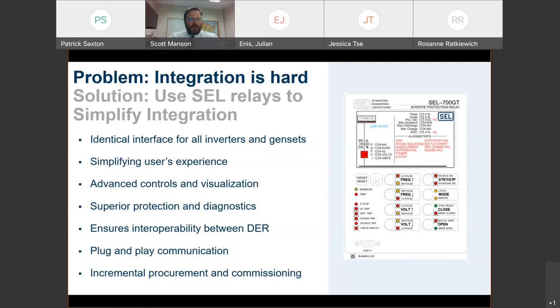Here's a great example, bullet point number two. Put yourself in the shoes of a utility technician. They have a truck full of laptops, full of tools, full of drivers, full of communication cables, and they have to maintain a fleet of inverters and generators and substation equipment and reclosers. It's an enormous amount of equipment they maintain. In one case, one technician had over a dozen different inverters from different manufacturers of different eras to maintain.